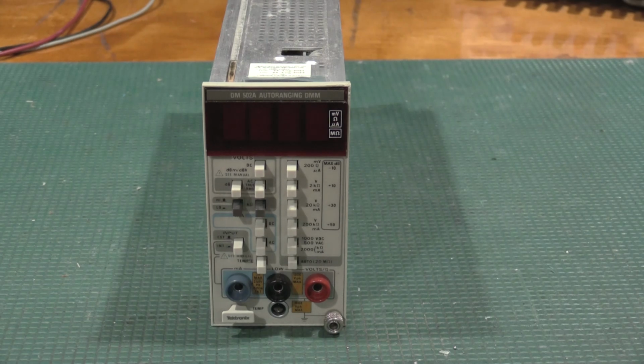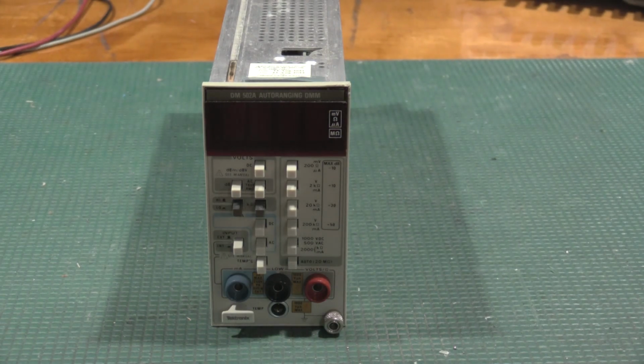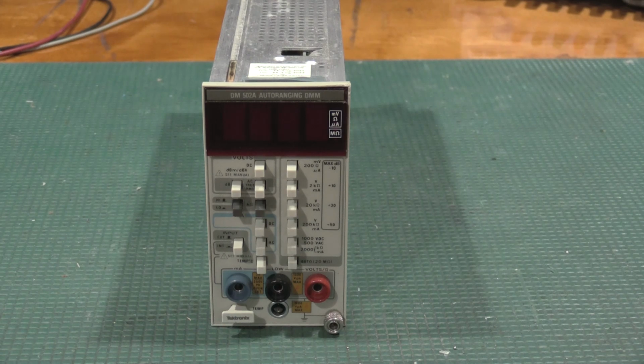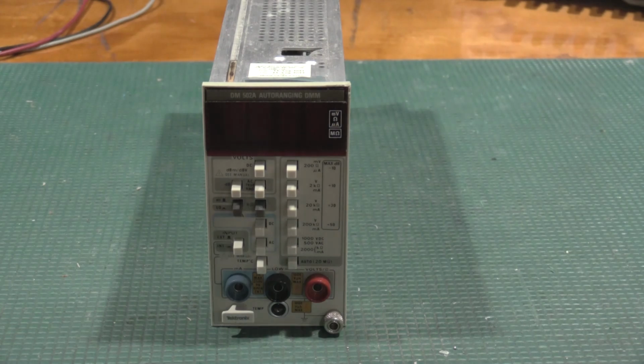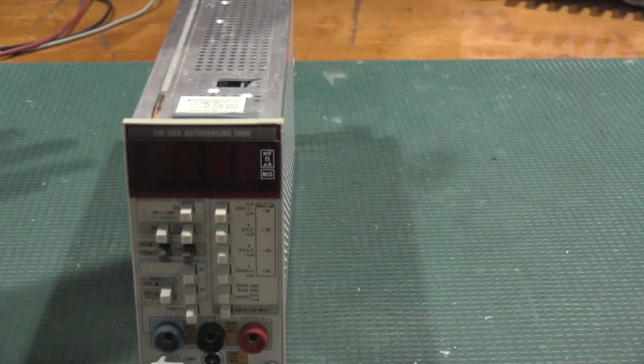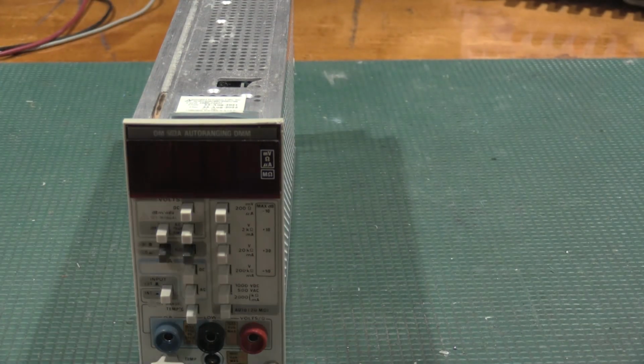So to facilitate that, I have a Fluke calibration standard, and actually 2 Fluke calibration standards, a 5200A with the associated power amplifier. You do need to get the power amplifier to get above 100 volts on the 5200A, and a 434. So I lean on those quite a bit for doing the alignments on these and to get these all topped up. There are more modern units that also need current ranges. This particular unit does not need to align a current range because it has just a shunt. And you pass a current through it, and it just measures the voltage drop on the shunt.